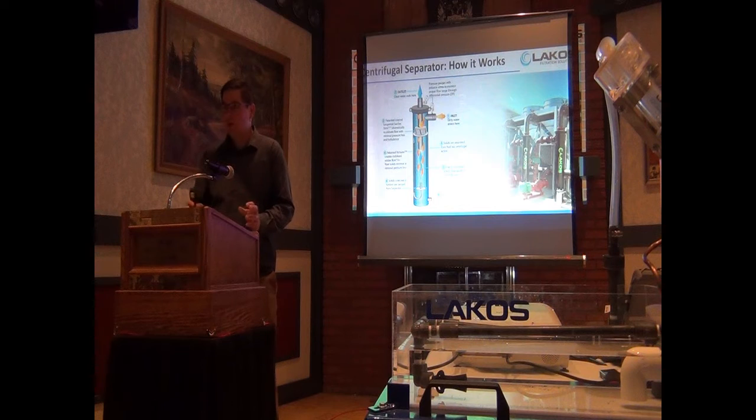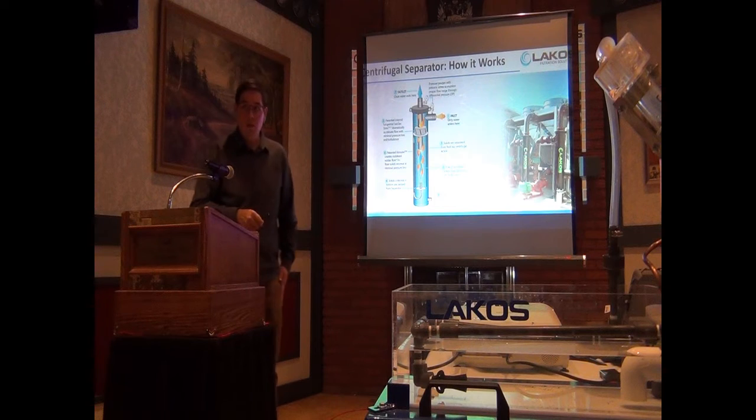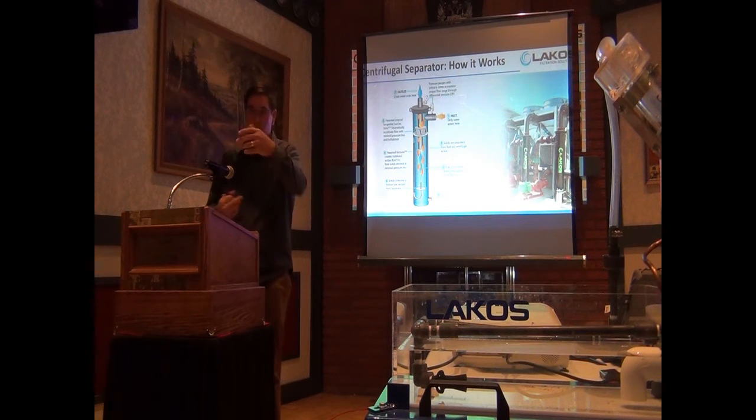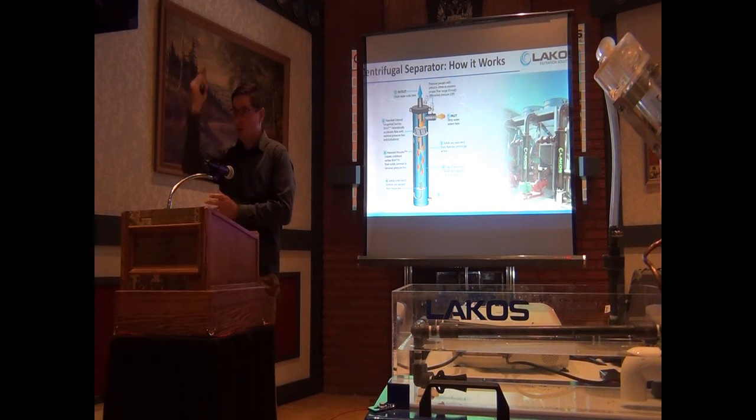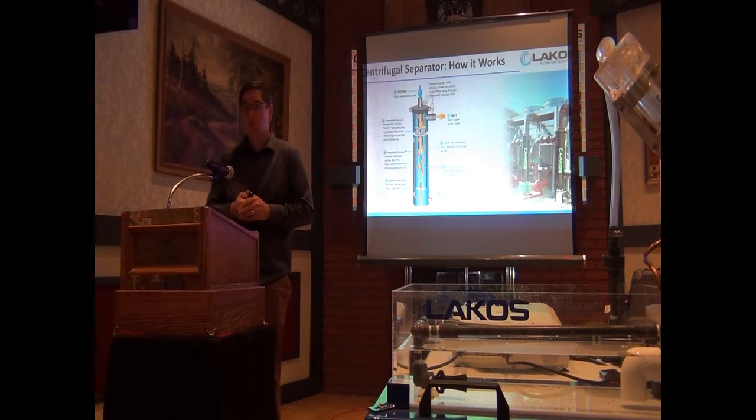That's an extreme oversimplification of what happens on the inside, as there are a couple steps of acceleration that occur. The first is as the water enters the filter, and the second occurs through a set of tangential slots, which further accelerates the flow and creates that vortex. If you imagine a tornado plowing through a field and pulling stuff up from the bottom, that's basically what happens, but instead of air being pulled around in the vortex, it's the fluid. So that's your condenser water.